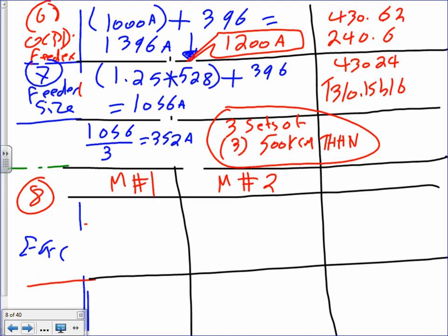For equipment grounding conductor, your reference is going to be table 250.122. That's the reference that you're going to be using. Okay, equipment grounding conductor for the first motor. Remember, we're doing equipment grounding conductor for the first motor. So we need an equipment grounding conductor for the first motor. What was the full load current of the first motor? We have 1,000 amp. Okay. So I have 1,000 amp.